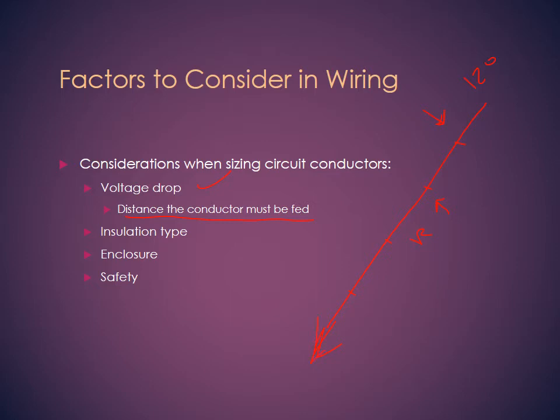Some charts also give you the voltage drop for each foot of that cable. So you have to pay attention to that, but most equipment is usually rated to work between 75 to 100 feet of length. If you go further than that, you might have to do something about the voltage drop. What are you going to do? You can change the wire gauge. You can go a little bit bigger, because if we have a small gauge and a big gauge of the same length, the big one will have less resistance. So that's another option. Or you can consult an electrician and see what is possible to do to increase the voltage. So we have to care about the voltage drop.